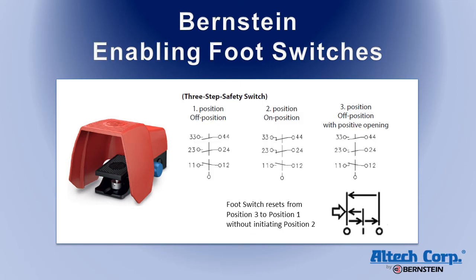Enabling footswitches are designed to allow an operator to override the safety systems of a machine for programming or repairs while maintaining local control as required by safety standards. Similar to the safety footswitch, it has a three-position contact arrangement with on in the middle position. They are available with standard release or latching with a button release. When the pedal is released from the bottom position, it does not make contact with the center position as it is reset.